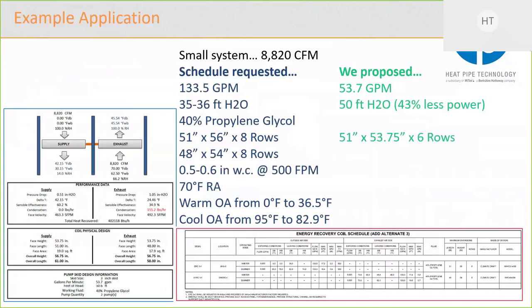I skipped the propylene glycol because obviously we're going to meet that requirement. The coils we're providing, it was two identical coils, and we actually used 6 rows instead of 8 rows. They also were around 0.5 inches. We had a slightly lower face velocity because we were able to fit a bigger coil into the system.